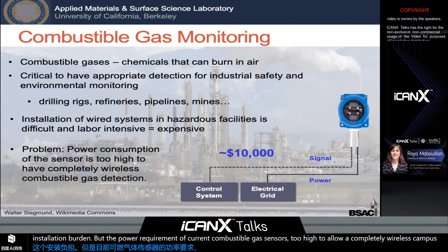One such sensor is a calorimetric sensor, whereby the presence of the combustible gas of interest causes a temperature change in the sensor due to the heat of combustion that I've highlighted in red in this equation. One commonly used realization of such a sensor is called a pellistor, consisting of a platinum wire coated with a porous alumina coating that has platinum nanoparticles dispersed on it. The platinum nanoparticles, as you may know, have high activity for hydrocarbon oxidation. The heat of combustion that is produced causes the temperature of the platinum wire to increase, which in turn causes its resistance to increase due to platinum's positive temperature coefficient of resistance, TCR.